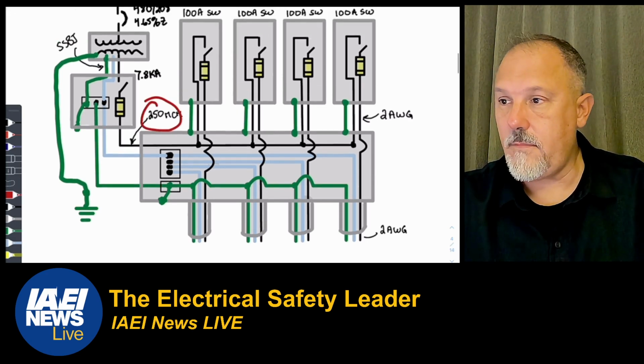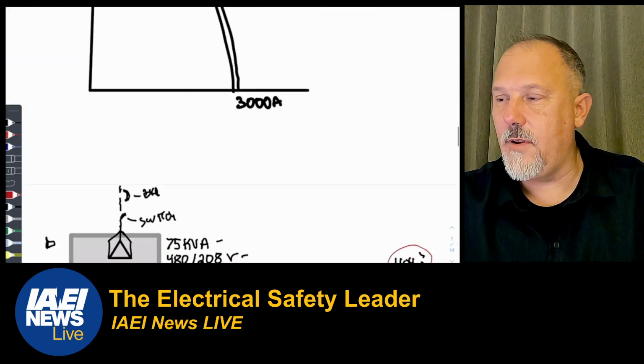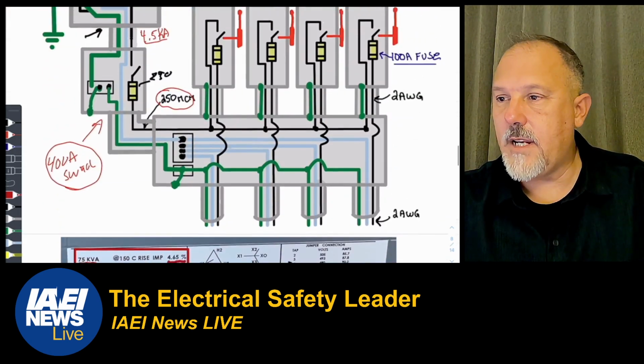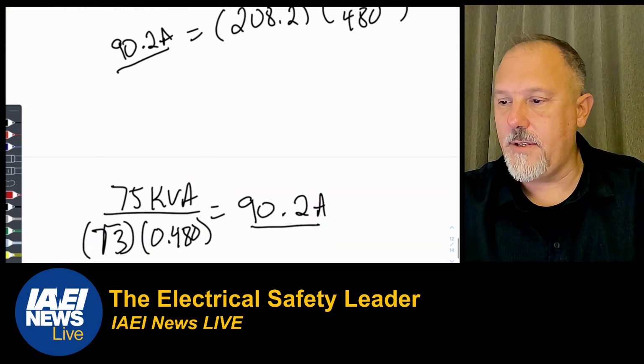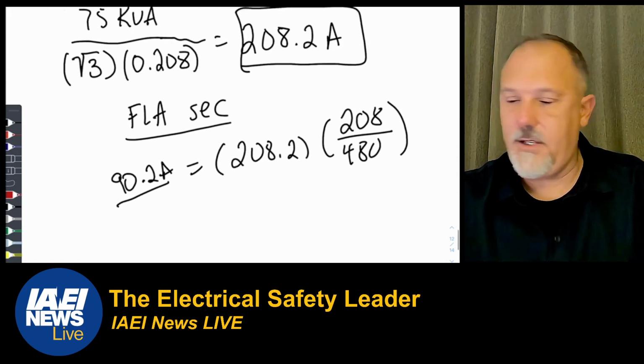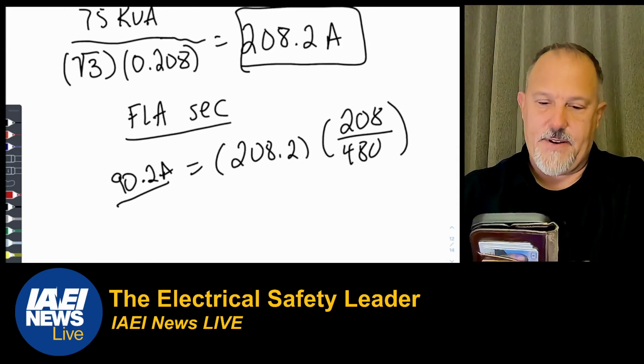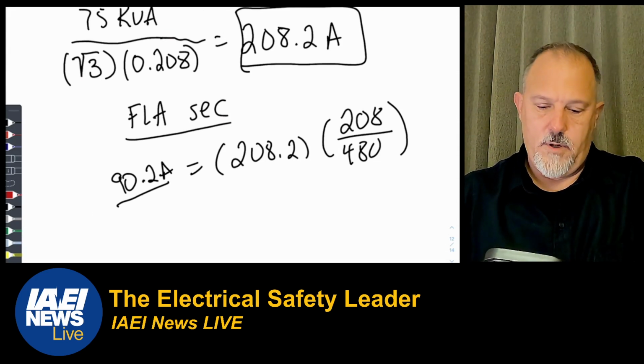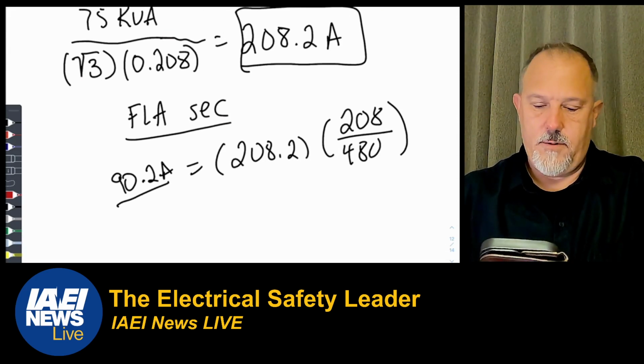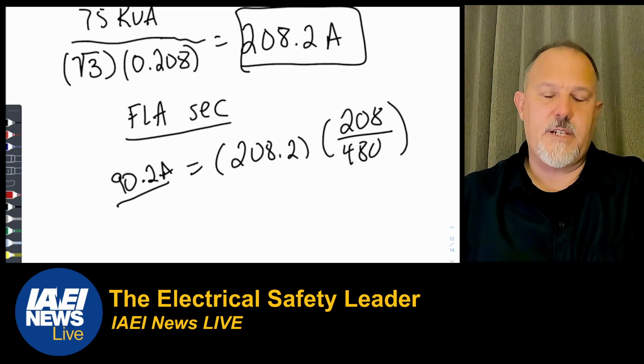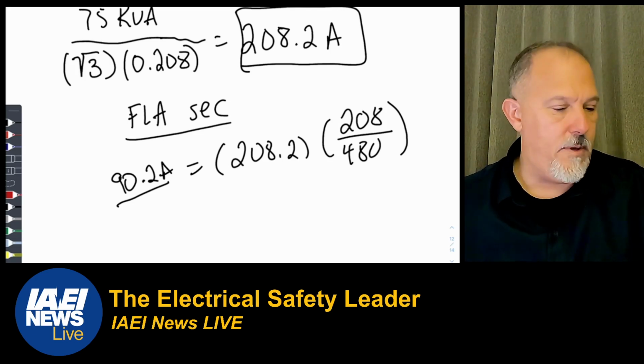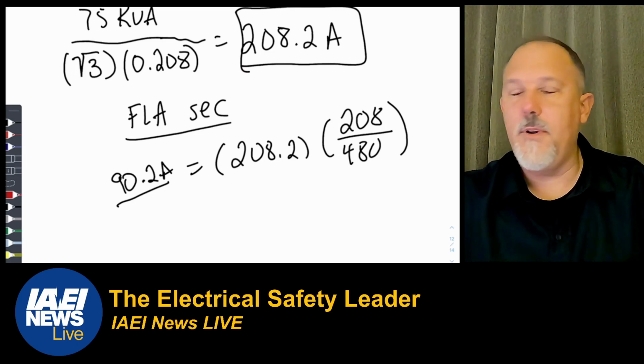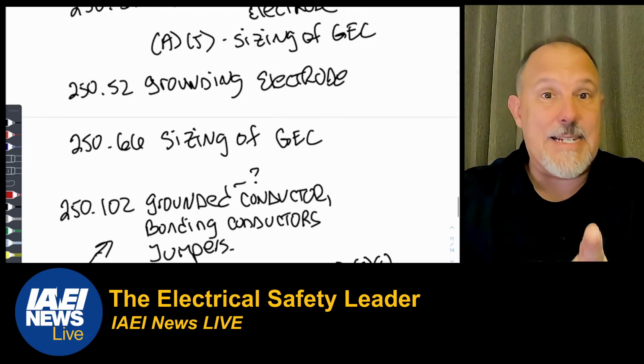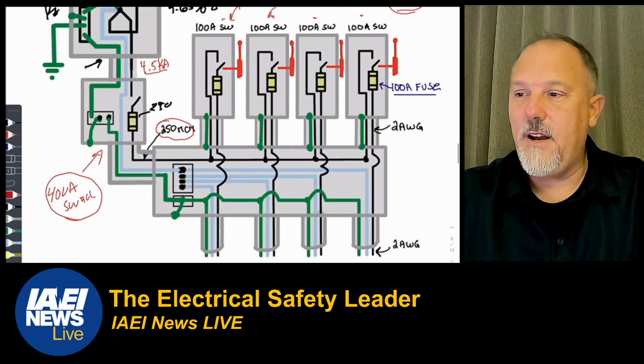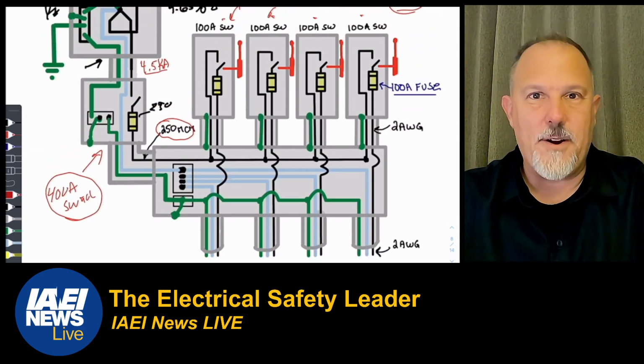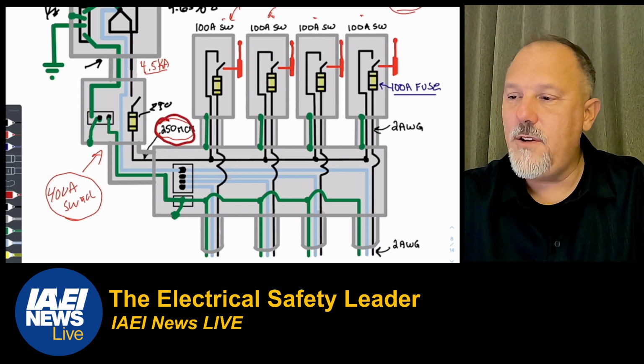Well, let's think about that. What's the secondary full load amps? We did the calculation. Remember, what was it? 208.2 times 1.75, 364. I can go to the next higher, 400 amp. So I could put a 400 amp switch on the secondary, which is what they did, right? They put a 400 amp switch in here with 400 amp fuses, but they only put 250 MCM.